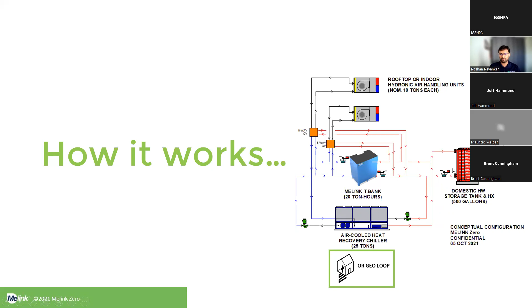A simple schematic of how this works: you could pair a thermal energy storage system with either a ground loop or an air-cooled heat recovery chiller. During downtimes, use these systems to charge the battery, and during the day just circulate water through it to run your indoor units or rooftop units. This could also be paired with hot water storage, using thermal energy to transfer heat between these two systems and using Geo to top up the battery, so to speak, when the balance isn't there.